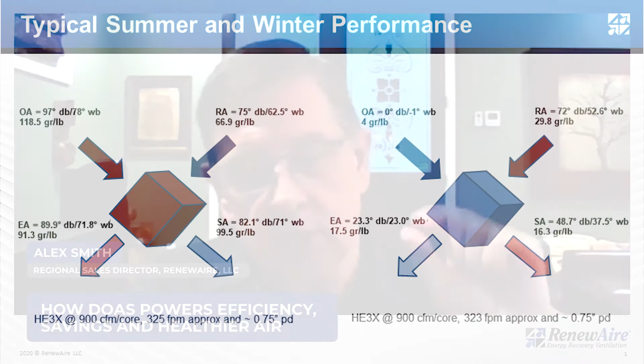And it is that difference which gives you your dehumidification capacity. So it stands to reason, if you've not got very much difference between the two, you're not going to get very much dehumidification capacity. So one of the things that a DOAS unit has to do is to be able to dehumidify to a lower dew point than that. So if, for example, you dehumidify down to a 52-degree dew point and you supply that into the space, now that corresponds to something more like 57 grains. So now you've got a much bigger delta between the grains in and the grains out, that actually gives you some dehumidification capacity. And there are formulas for calculating the airflow and the load and what the grain delta needs to be in order for you to dehumidify all of the outdoor latent load and all of the indoor latent load. And it's a common mistake and probably the biggest difference in terms of performance criteria between a DOAS unit and a conventional HVAC unit.